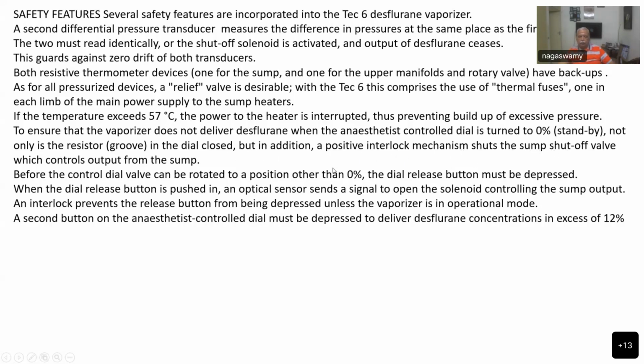And that is the purpose of having the optical sensor, so that when you operate the dial from 0 to 1% and 2%, when you turn the dial on, that is sensed by the optical sensor, and the shut-off valve first opens and then only the gas can come out. So it is a double protection. So at 0%, no vapor will be present outside the sump.